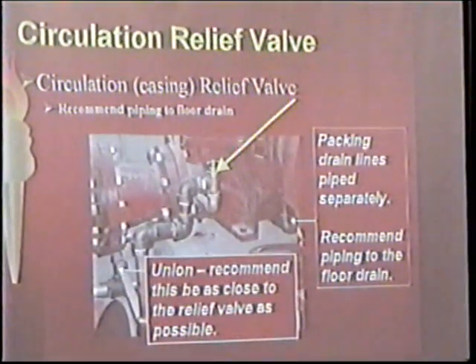this is the circulation relief valve. The code book, by the way, now states that these packing drain lines and this discharge shall not be connected. And we still find a few of those a year where the fitters have piped them that way. And honestly, they'll almost always pull out a drawing and say, see, that's the way it shows it.